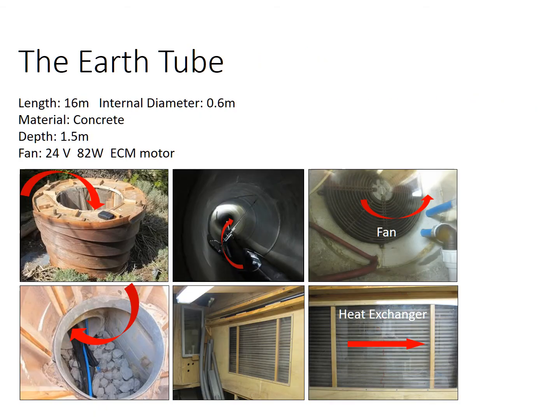So let's look at the earth tube in a bit more detail. The earth tube is 16 meters long, 0.6 meter diameter, made of concrete, 100 millimeters thick and about 1.5 meters down. The fan that drives it is very efficient, an ECM motor, DC, and the air goes down through this intake here, which is normally covered. There's an insect screen down into the ground, and there's the pipe, the start of the earth tube proper.